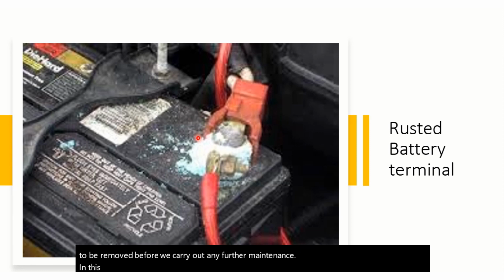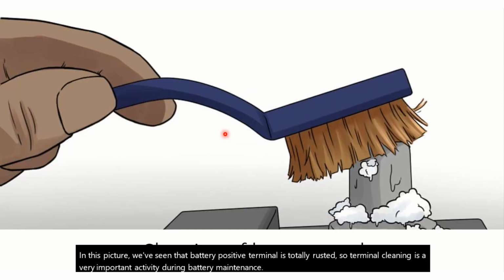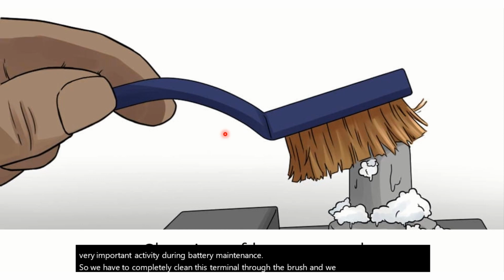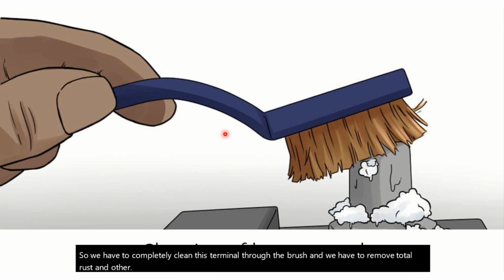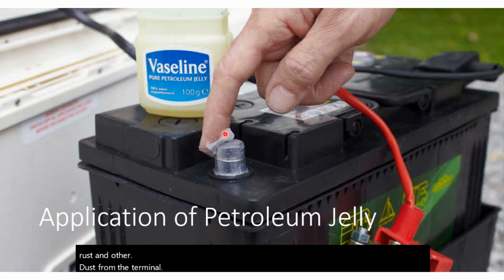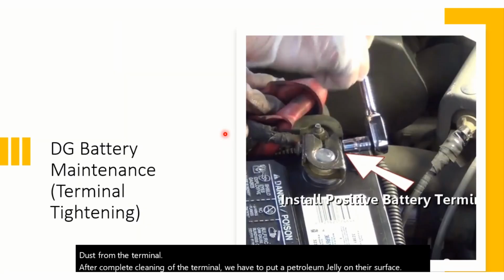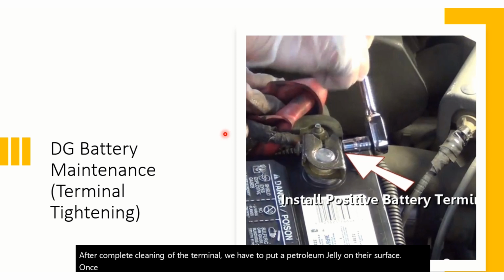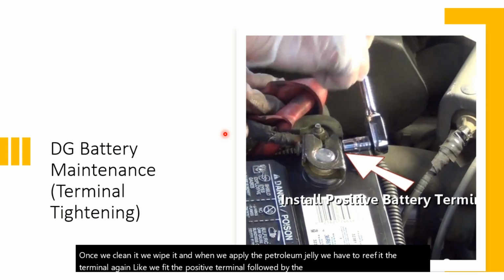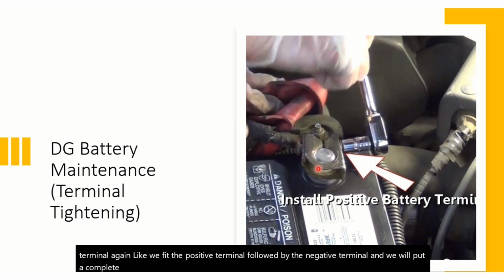In this picture we have seen that the battery positive terminal is totally rusted. So terminal cleaning is a very important activity during battery maintenance. We have to completely clean this terminal with a brush, and remove all the rust and other dust from the terminal. After complete cleaning of the terminal, we have to put petroleum jelly on its surface. Once we clean it, we wipe it, and when we apply the petroleum jelly, we have to refit the terminal again, fitting the positive terminal followed by the negative terminal, and we put complete tightness here so that there should not be any heating, spark or arc during ignition.